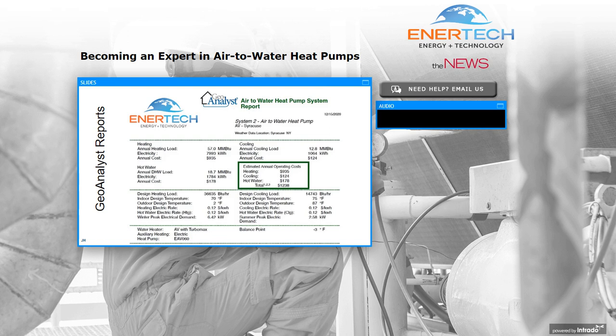In this particular area, you can see there are an awful lot of hours. In fact, in this case, there's 1 hour at minus 13. This heat pump will not shut off at all, no matter how cold it gets. And I guess it could be below minus 13, but at least from a design standpoint, it would be very, very unlikely. We only have 1 hour there, so the heat pump would run that entire time and provide us with how much capacity we can expect from the heat pump versus how much backup we need. There's also a report that shows operating costs. So now this takes all that information and puts it into dollars and cents.